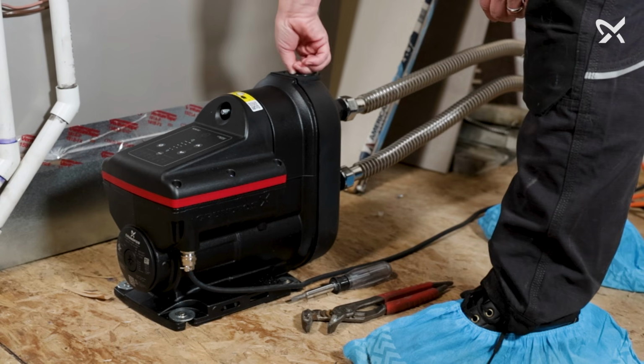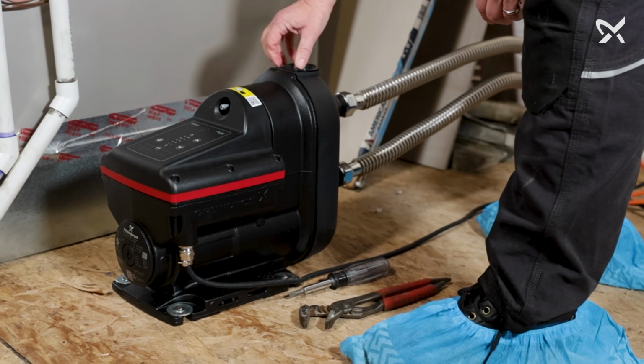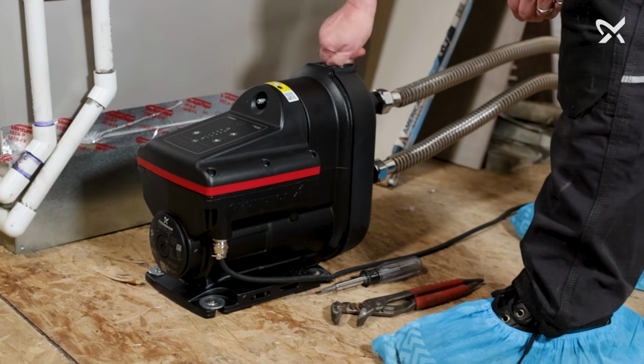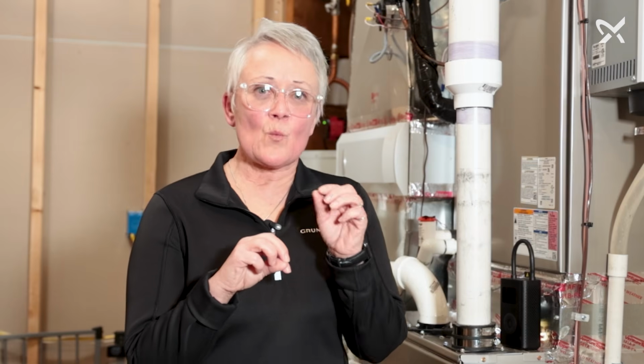And just like any other pump, it needs to be primed, which means we have to fill the pump with water, right? If you're working on a suction lift application, you may have to physically remove the priming port cap and pour about a half a gallon of water inside the pump to properly prime it. If you're in a positive pressure situation, however, you can simply turn on the water and open the priming cap ever so slightly to allow the air to escape. Once you start to see the water reach the cap level, go ahead and tighten it back down and your pump is primed.